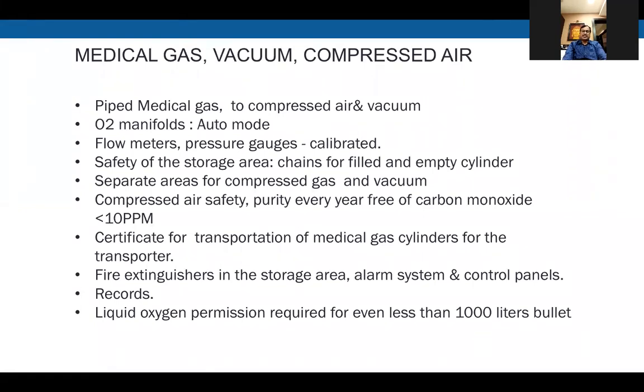So in oxygen, if you see, we have to have a right bank, left bank, and emergency bank. Similarly, in nitrous oxide, we have to have a right bank, left bank, and emergency bank. Most of the hospitals, you will find, cut corners in this also. They will not deploy these banks with the correct line pressure, which can be dangerous for the patients, especially those which are controlled directly through the central manifold. As an alternative to the central manifold, now we have liquid oxygen tanks. As I have already shown, liquid oxygen tank regulations have changed. So even for less than 1000 liters, you have to take permission. Also, among the alternatives which have come up, I have shown that pallets have started coming into the hospital.